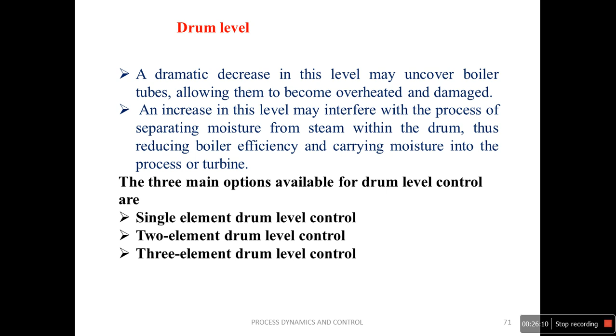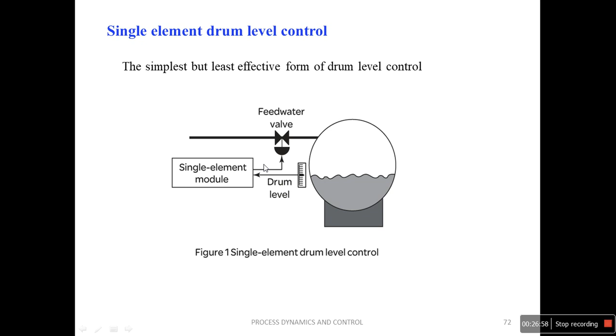First, the single element control is the simplest but least effective form of drum level control. Here we take a normal feedback control only. The drum level is measured using a level transmitter, a level sensor, and given to the controller, where it is compared with the desired level. The controller produces an output signal that varies the feed water flow rate, which will bring the drum level to our desired value. Very simply, we are going to control the drum level.